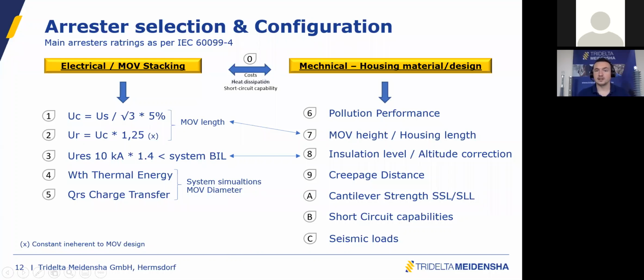Now comes the mechanical topic, the selection of the housing. One of the key features is the pollution performance. It's very common that when you have high pollution, very heavy contamination, you look for silicone housing, silicone material, because of its hydrophobicity properties. Then we have to look at the length of the housing to make sure that the MOV column defined from the electrical configuration will fit inside the housing. Then we look at the insulation level to compare the safety margin between the insulation level of the housing and the protection level of the active part.